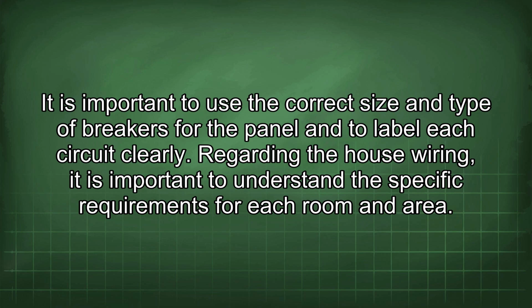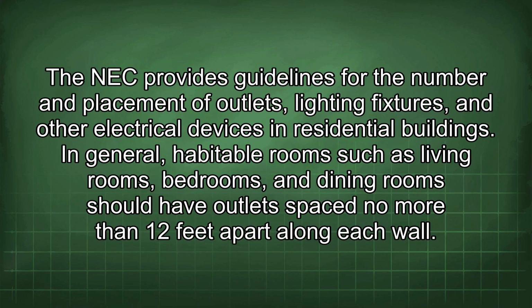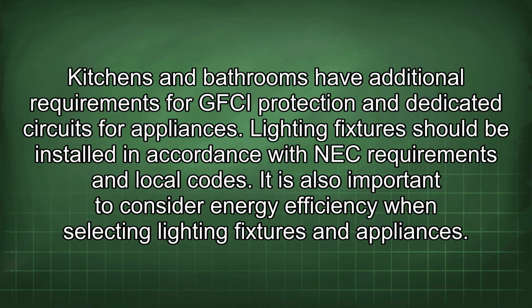Regarding the house wiring, it is important to understand the specific requirements for each room and area. The NEC provides guidelines for the number and placement of outlets, lighting fixtures, and other electrical devices in residential buildings. In general, habitable rooms such as living rooms, bedrooms, and dining rooms should have outlets spaced no more than 12 feet apart along each wall. Kitchens and bathrooms have additional requirements for GFCI protection and dedicated circuits for appliances. Lighting fixtures should be installed in accordance with NEC requirements and local codes. It is also important to consider energy efficiency when selecting lighting fixtures and appliances.